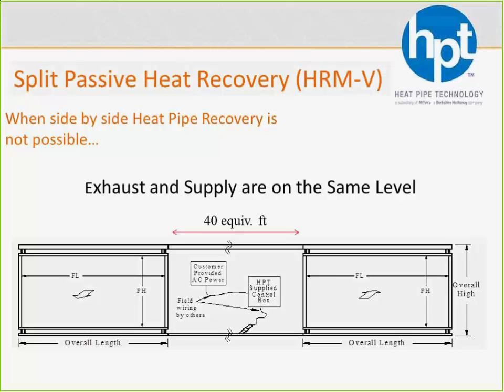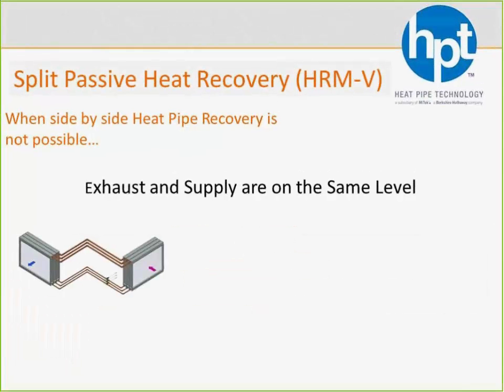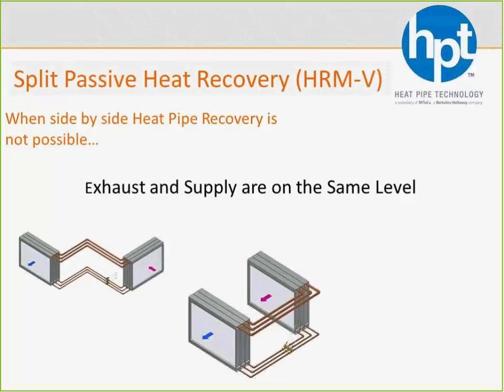So we can actually run up to about 40 equivalent feet, and that equivalent feet isn't just distance from one airstream to the other. That's the actual piping run and resistance that the refrigerant's traveling. So when we add some elbows in there, that's going to add some resistance. And if you have to zigzag across the floor, it's the actual run that refrigerant is making. So whether we zigzag across the floor or even go from one parallel airstream to the next, it's all the same to the heat pipe as long as it's within 40 equivalent feet.